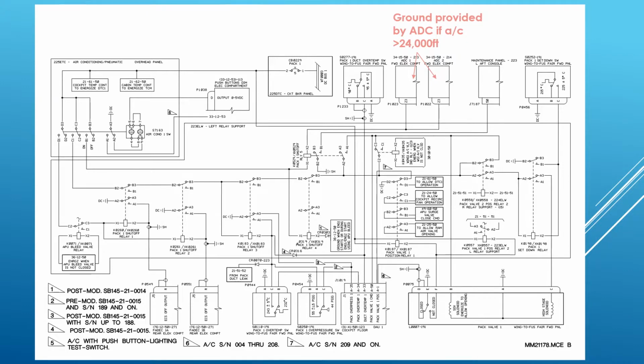First of all, the pack valve itself, what we're looking to control, is down in the bottom right hand corner of the picture. You'll see there are two solenoids on there and they share a common ground. One is basically the on-off solenoid, the one on the left. The other one says high stage solenoid, that's the solenoid that causes it to go to the high stage mode or the high flow mode. If it's energized, it goes to high flow mode. If it's de-energized, it goes to low flow mode.